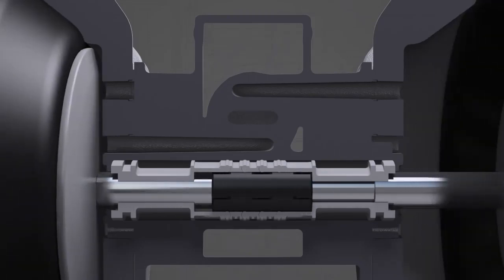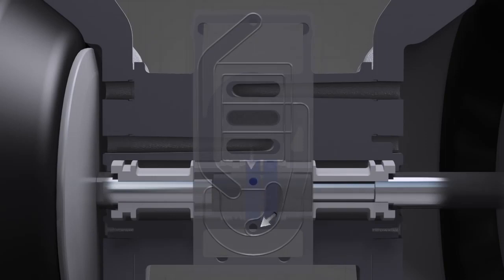Pressurized air enters chamber three in the middle of the pilot valve sleeve. Chamber three is always under pressure. When the pilot air valve travels far enough to the right, chambers three and four are connected. This allows the pressurized air from chamber three to pass through and exit chamber four, which moves the main air valve upward.